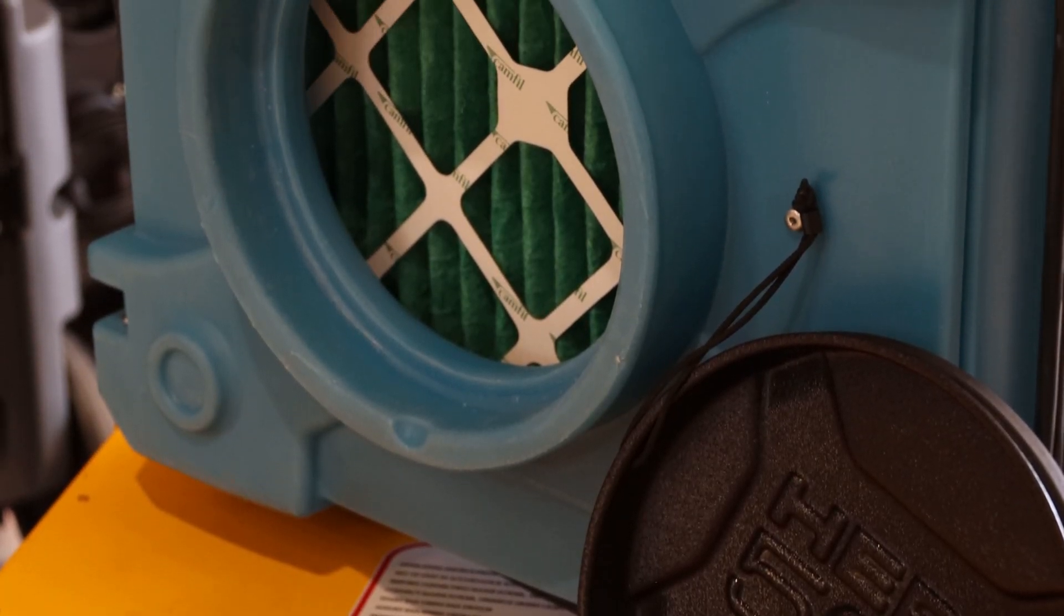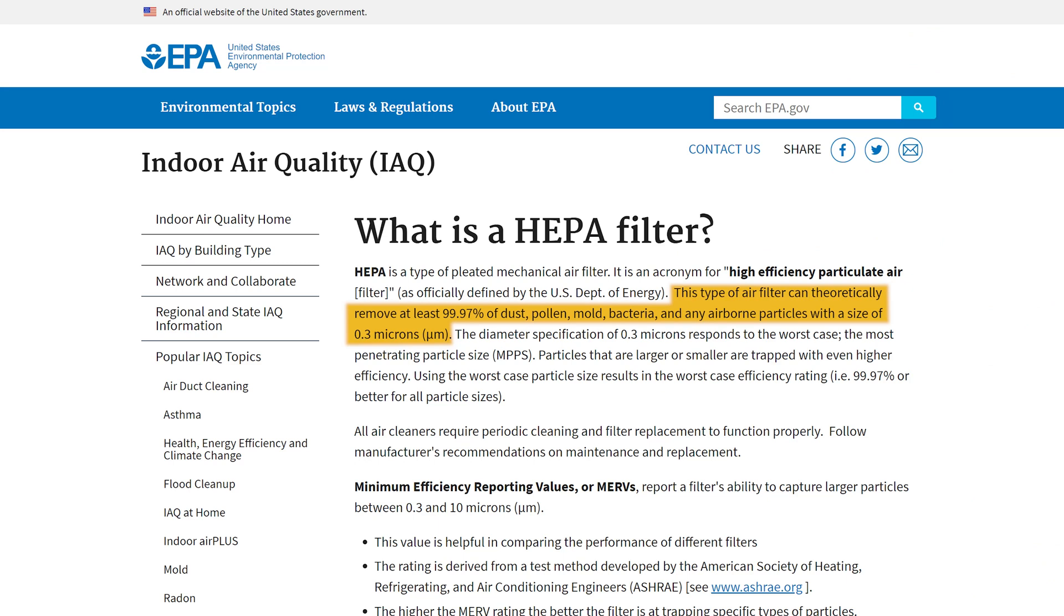A popular option is the HEPA air scrubber. These pull air through a series of filters that removes 99.97% of airborne particles 0.3 microns or larger. There are also extra filter options available for issues like odors or for even finer particle filtration.